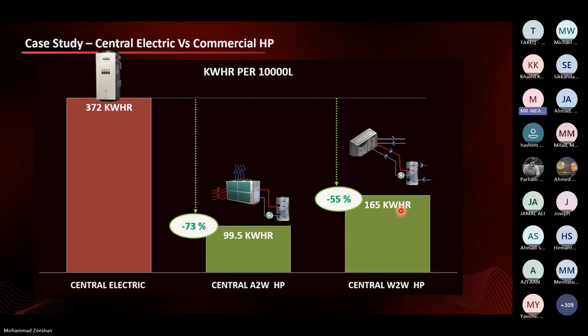Now, people who see this usually ask me: why is water to water only 55% compared to air to water? That's mostly because with water to water, during winter months, when there is not enough flow of chilled water, you have electric backups working all the time. So this is why your electric element consumption goes up, and the saving goes down, and this is how the systems operate. So out of three options, air to water is always the first priority. However, certain clients have requirements, or don't have space, then they go for water to water heat pumps, which suits their requirement.